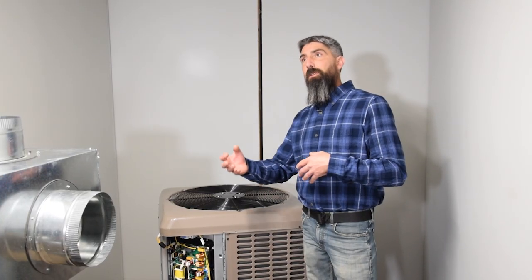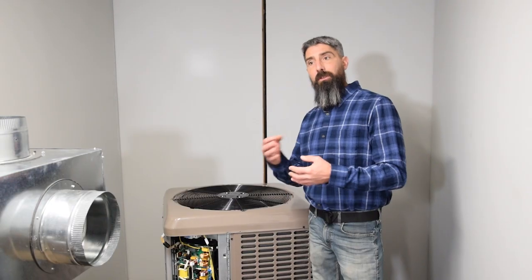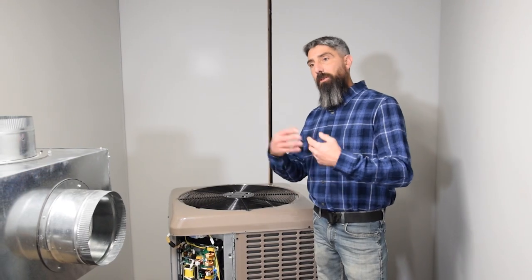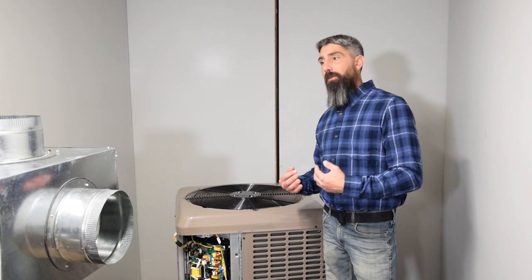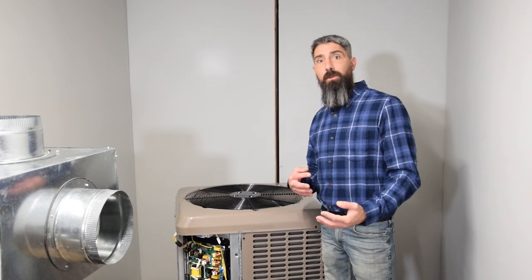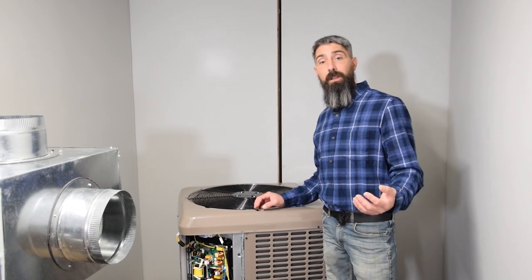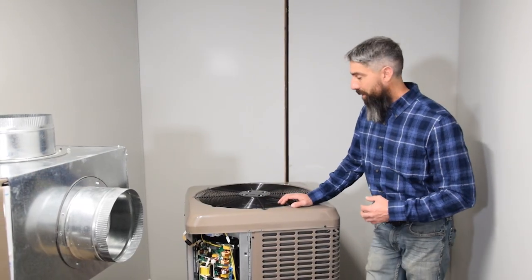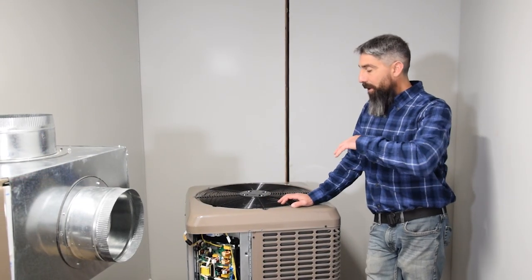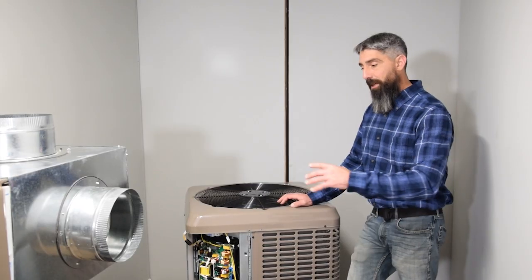Hopefully if your auxiliary heat strips are sized appropriately for the machine, then you won't really notice it that much. It'll be about room temperature. If you have a four ton unit with a 5KW heat strips on there, it's probably going to feel pretty cold. But those are things to take into account.